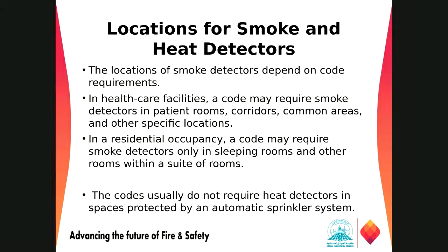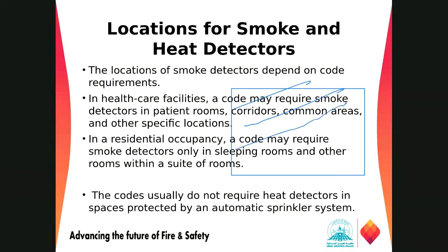This is why the IFC code or other building codes may not require a smoke or heat detector in any kind of fire alarm system, such as smoke detectors and heat detectors in unoccupied warehouses. So if there is a warehouse, it might not need a heat detector or a smoke detector if it is protected by the automatic sprinkler system, because the moment it fuses, the fire will be extinguished or brought under control by the sprinkler system. At the same time, the flow switch will give a signal to the panel and someone will come to control those areas.